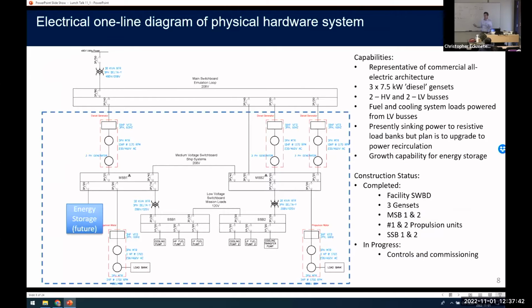So then diving into the physical hardware system that we have in the laboratory, I chose to start with the electrical diagram. In the lab space itself, we start with a 480 volt input feed. We run that through a delta Y transformer, which steps us down to 208 volts. This also isolates us from the grid and allows us to put imbalanced loads on the system without causing a negative effect on the utility power.